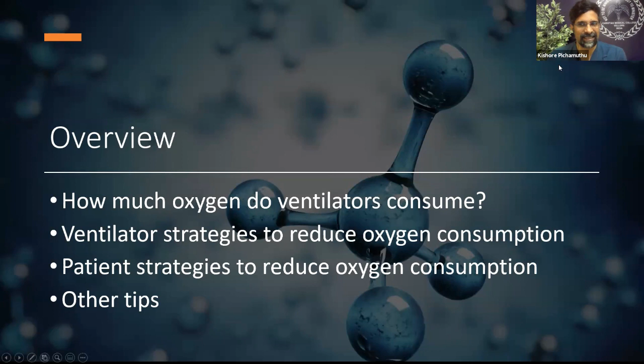So it's very easy to calculate the oxygen consumption of ventilators. We must remember that the total gas outflow consists of mainly the minute ventilation. That's of course tidal volume times respiratory rate. But there are some other components as well. There's a bypass flow. That's a constant flow that is sent through the circuit in addition to what is required by the patient. And that is some information that may be available on the screen of the ventilator or in the manual. It's a fixed flow. And then, of course, there is leak compensation that most ventilators have.